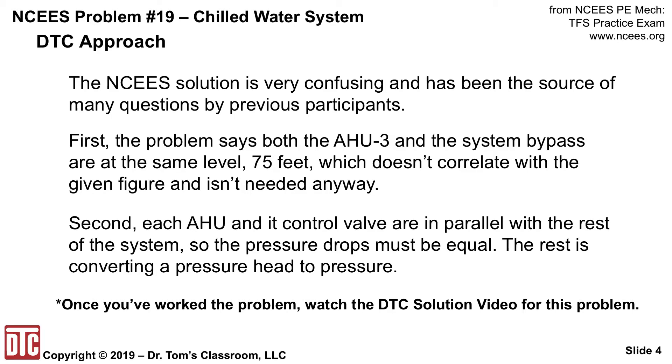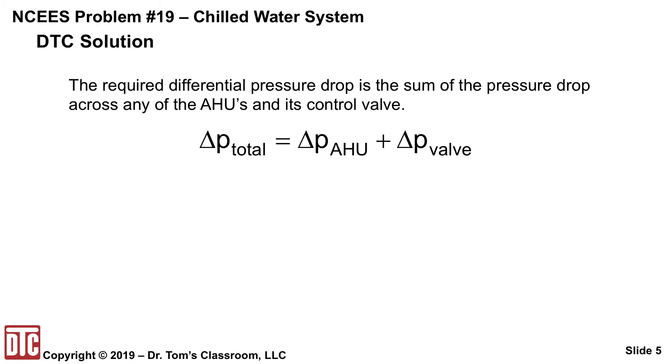Okay, let's see what we really need to do here. Well, the required differential pressure drop is the sum of the pressure drop across any of the AHUs and its control valve. So the total pressure drop is ΔP_AHU plus ΔP_valve, and we're given the valve is 5 psi.